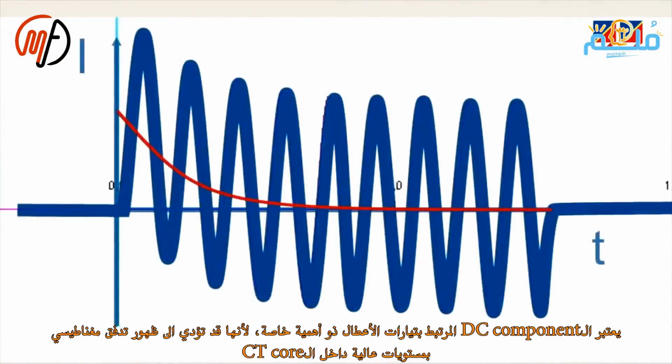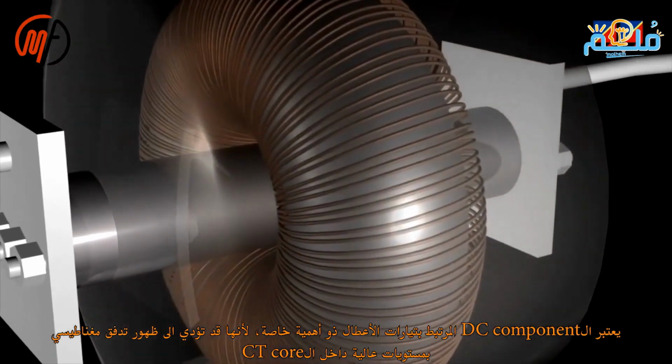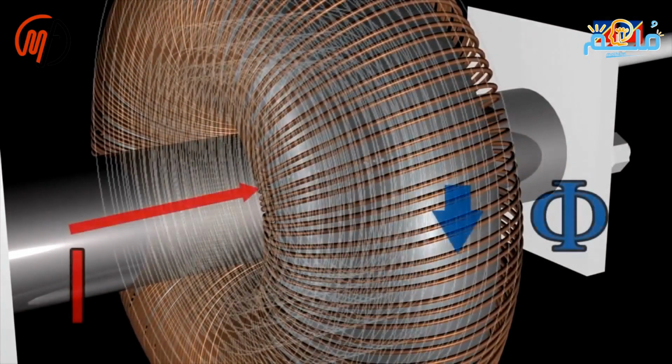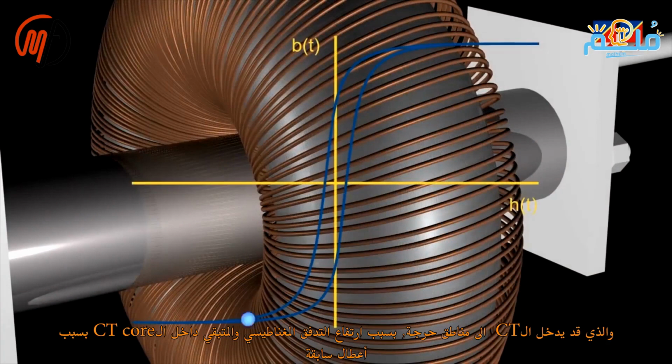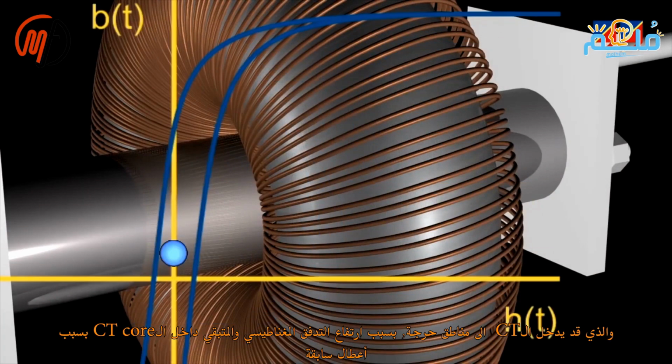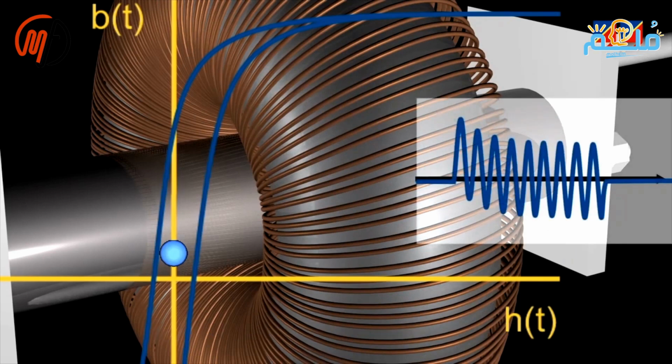The DC aspects of a three-phase fault are very important because they can lead to a significant level of magnetic flux in the CT core. An important situation occurs if the CT core has a large magnetic flux from the previous fault, and then a second three-phase fault occurs.